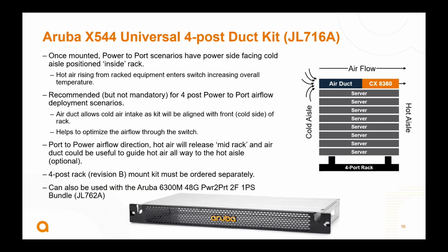And that brings me to another point. If you noticed on that first slide, we have switches with 16 ports, 32 ports, yet look at the dimensions of the switches - the dimensions of these physical boxes are all the same. There's a purpose for that, in that we can allow them to use this single air duct, which we're also going to be introducing with the 8360. This allows us to ensure more optimal airflow going through back-to-front airflow mounted switches, because of all the server hot air that rises up through that rack. This air duct will help ensure we're getting cold aisle air drawn into the switches, making it more optimal. Another thing to note with this air duct is, because of the dimensions, it can also be used with the 6300 back-to-front out-of-band switch in the data center. So it's compatible with that one too.